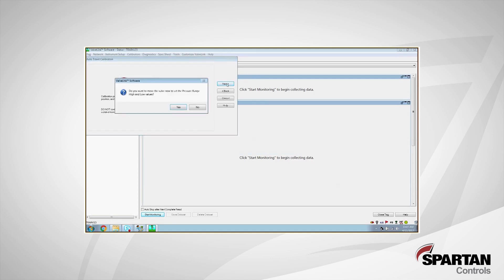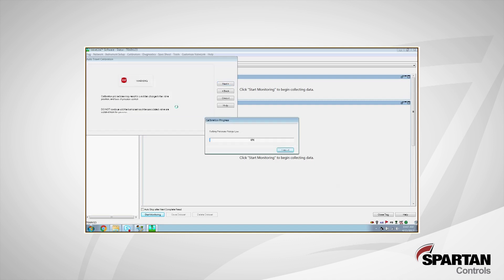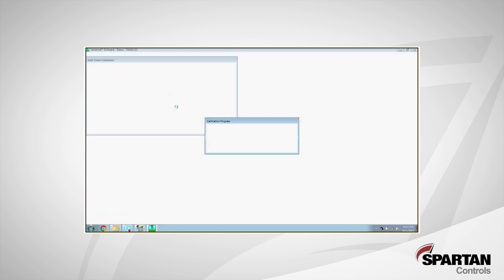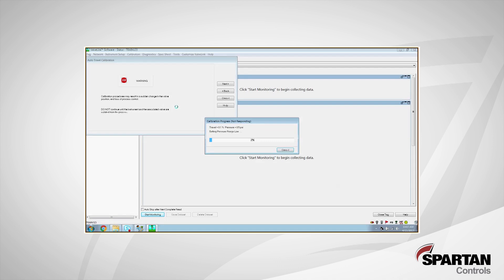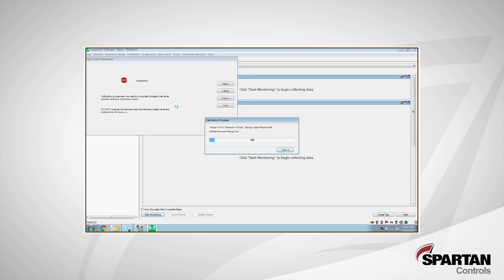Now it's asking me if I want to set my pressure ranges high and low. This is used when you go into pressure control mode. So I'm going to want to select yes if I ever choose to go that route. In newer versions of the DVC and the software, it actually just does this automatically for you and just selects yes. And right now you can see that it's going to be mapping out the pressures as it leaves our valve seat as well as when we hit our fully open stop so that it can span that 4 to 20 milliamp input if you ever choose to go into or automatically go into the pressure control mode.